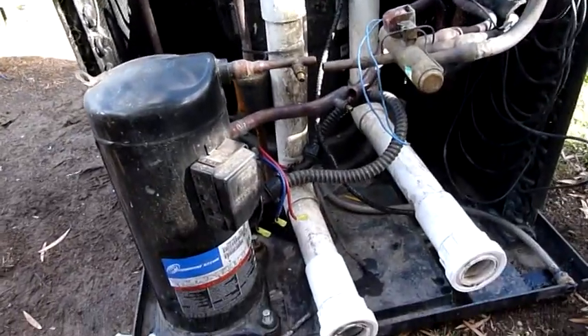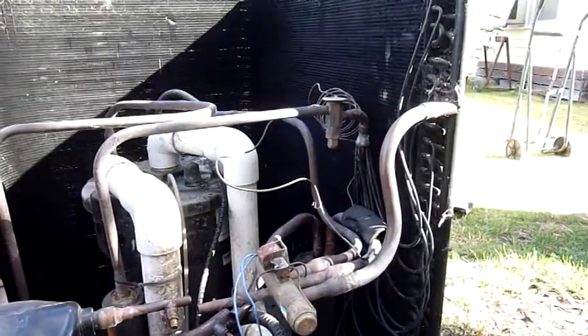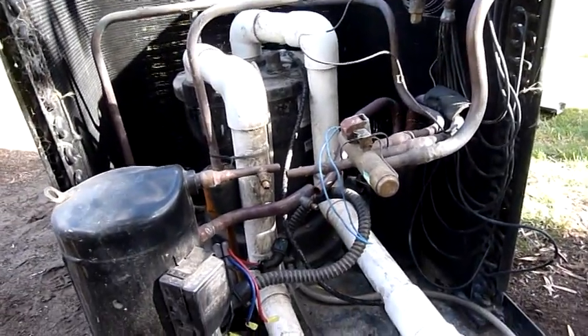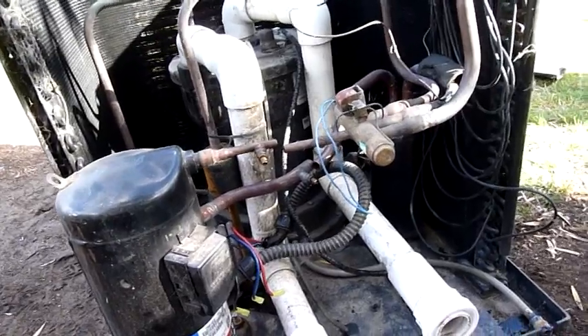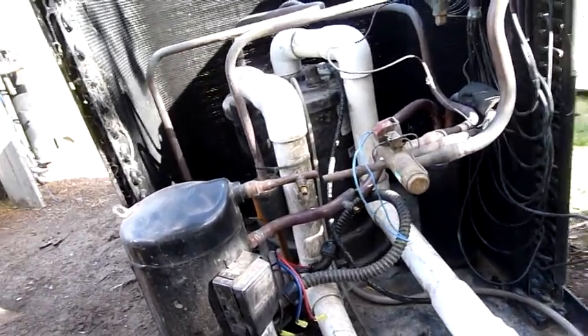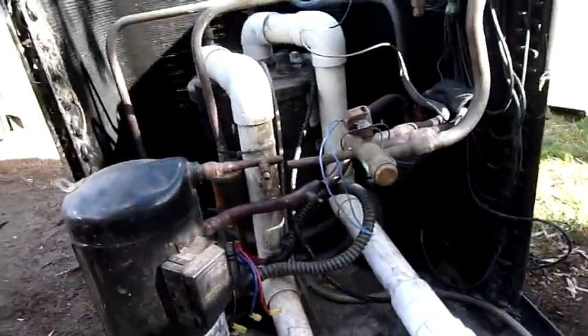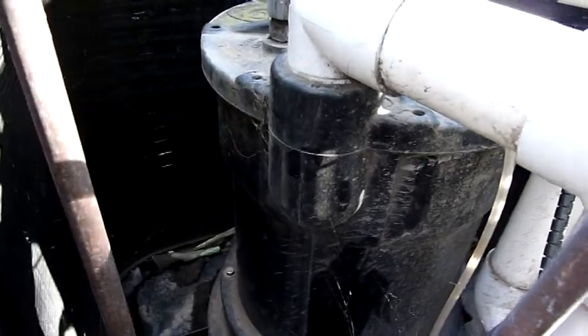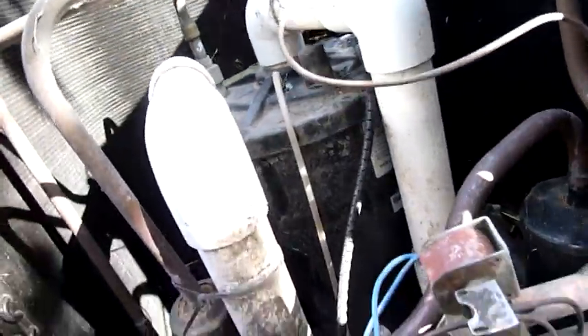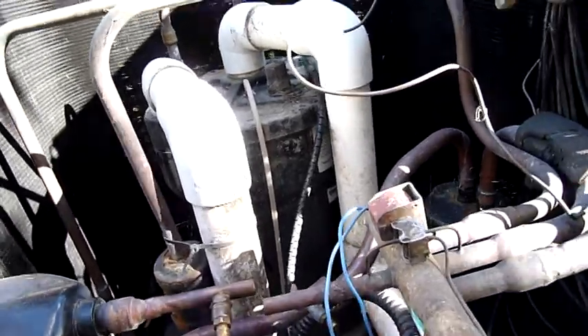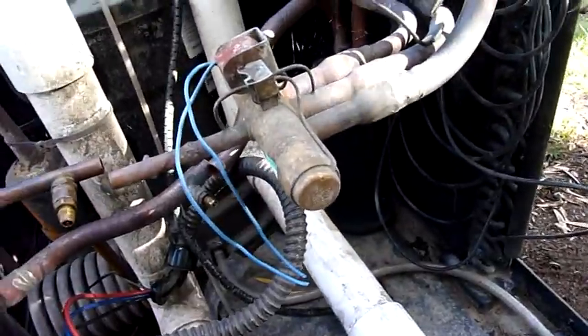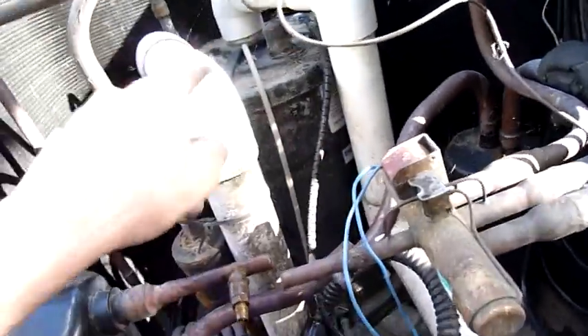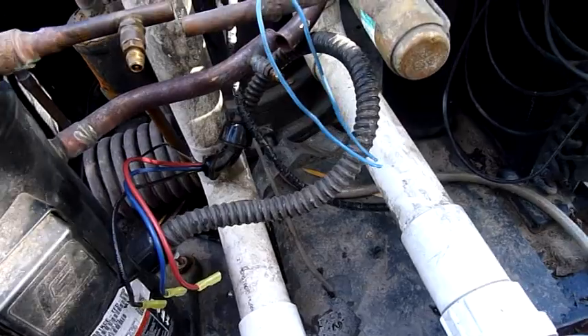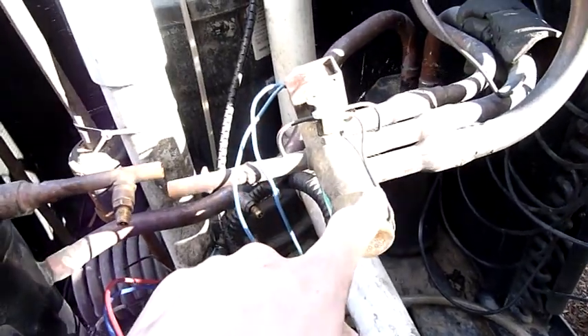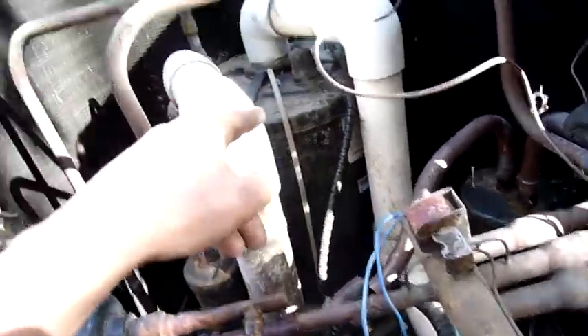Okay, so as far as water chiller anatomy goes, you really take the same principle of a reverse cycle or heat pump air conditioner and just apply it to water. Instead of having an indoor coil to exchange heat with air, you have a coil inside a drum or a tube which exchanges heat or removes heat from water. In this case it's removing heat, because it can run as a heat pump and heat the water going through it, like for a pool, which is what it was designed for. But we ended up using this one as a chiller, and all it does is absorb heat from water and exchange it out through the coil. So it's the same principle.